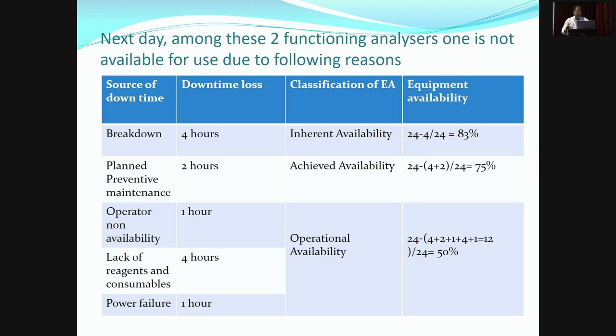Lack of reagents and consumables causes another 4-hour loss, and there's also a power failure causing another loss. So altogether, there are 6 hours lost due to other sources of downtime. When you calculate operational availability, 24 minus 12 total hours lost, the equipment availability is 50% for that particular analyzer. These measures are very important to identify the various sources of downtime and take appropriate measures.